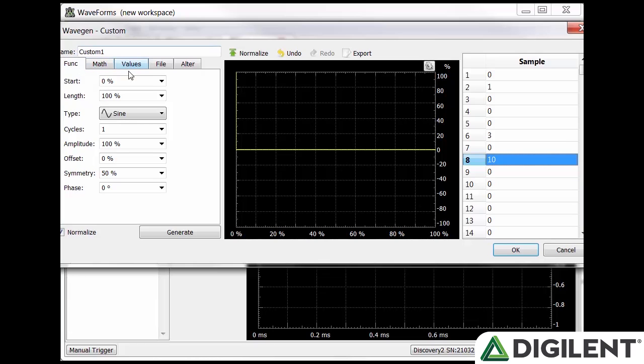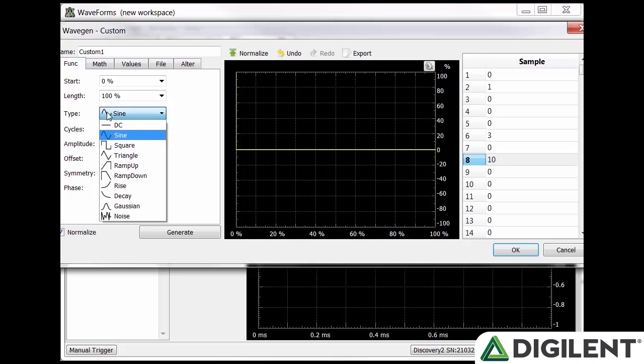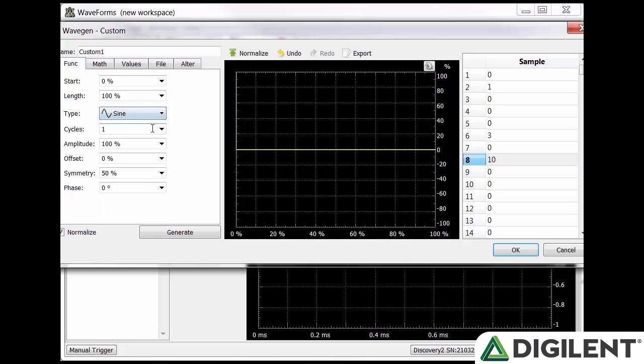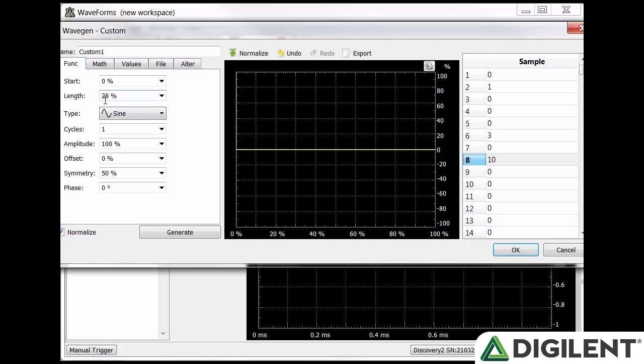On the left there are multiple tabs that allow you to define the waveform: function, math, values, file, and alter. The function tab has eight editable parameters. Start and length refer to the x-axis, where it starts and how long it will be. Type gives the type of the waveform. Cycle determines how many times the waveform will repeat. Amplitude sets the percentage of the available window the signal will use for amplitude. Offset determines the vertical center, and symmetry and phase have the same effect as before.